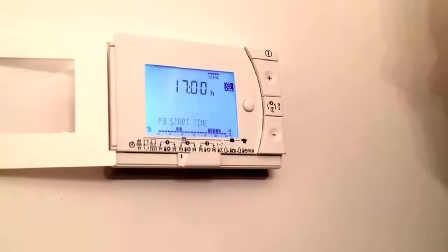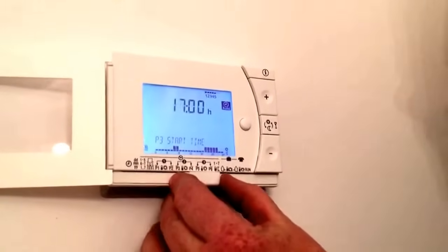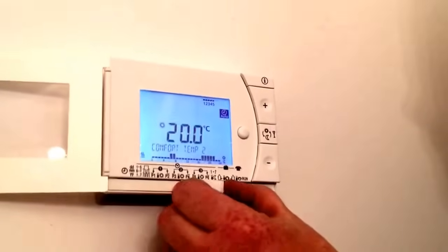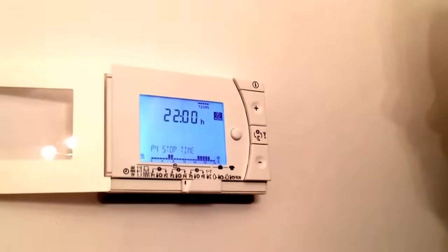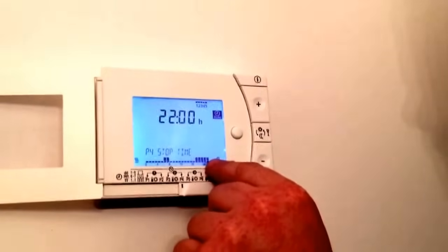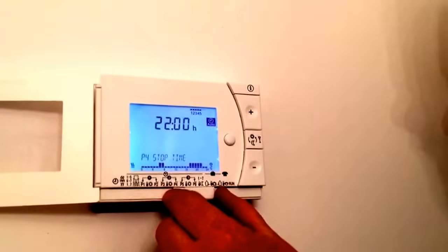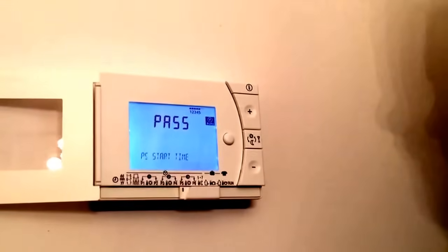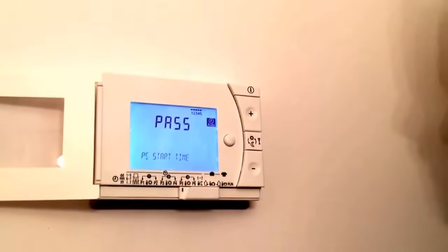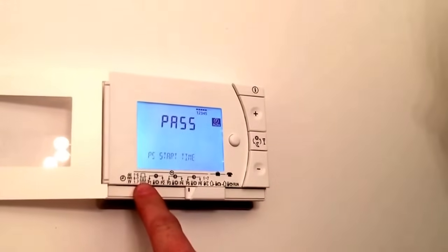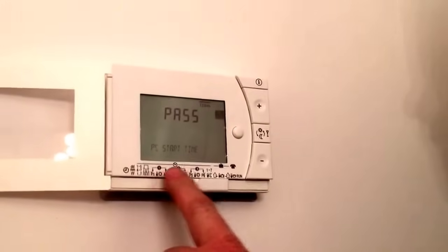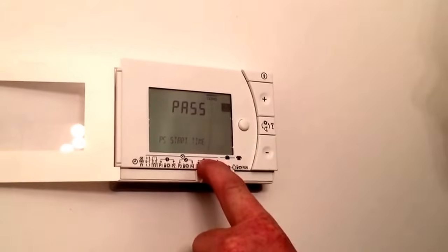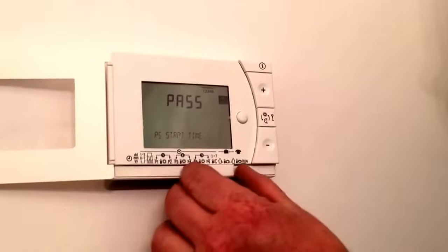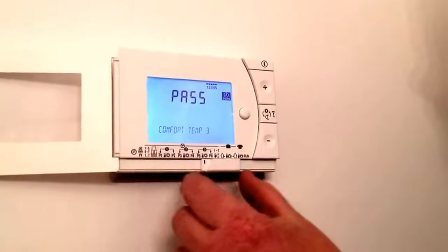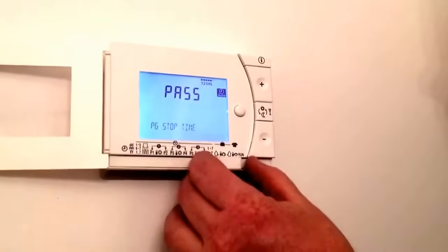We move on to P3 and that's, as you can see flashing now, the time it's going to come on in the evening, 5 o'clock. Saying again, we want it at 20 degrees and going off at 10 o'clock in the evening. It will correspond and flash on your program setting as to exactly which one you've got it on. We'll move to the next one. It says pass. Now, the reason it says pass is because we've only chosen two on-off times. So we've set up 1 and 2. It's not going to let us set up 3 because we've made an earlier selection of 2. So wherever it says pass, it's due to an earlier selection. So those next 3 will all say pass.